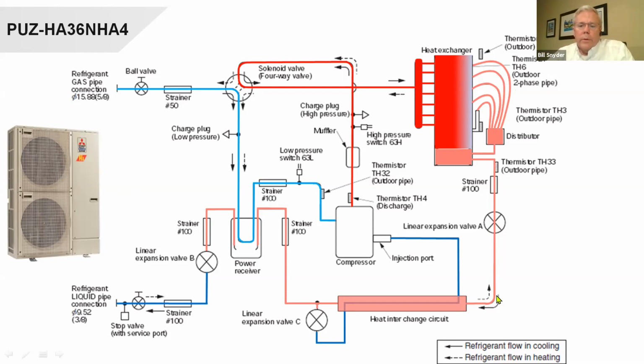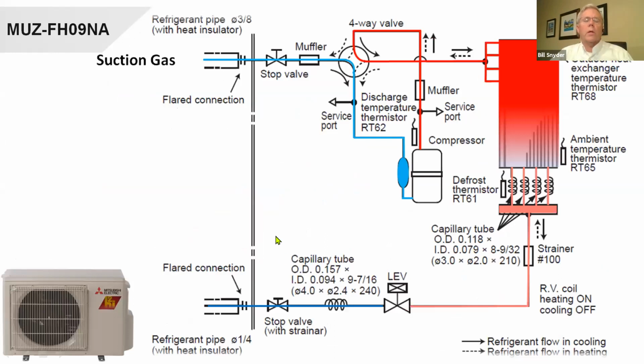Through a strainer, linear expansion valve, again through the heat exchanger, up through this hybrid power receiver, strainer, linear expansion valve, another strainer, and into the indoor equipment. Back in from the indoor equipment, through this power receiver, through another strainer, another thermistor here, and back to the compressor. It works very similar to the other one. The only thing is, it looks pretty simple on here. When you open up one of these pieces of equipment, you actually see everything's pretty tightly done. So just be aware that you want good installation techniques so you're not plugging up any of these strainers or cap tubes or anything.